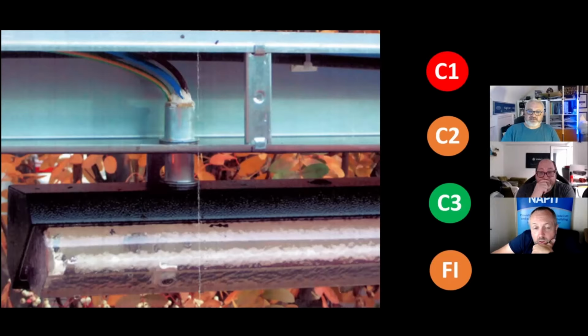This is the repairs they made. For me, this was a C3 - it just needed improvement. Is there evidence of water? Yes, because the actual fitting started corroding within 6 months of finishing. They were corroding internally outwards, which is a problem that manufacturer has - Neil will agree with me on that. This was a poor design, poor selection and erection. It wasn't the electrical contractor's fault, it was the designer's fault.